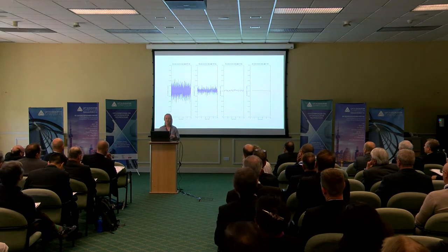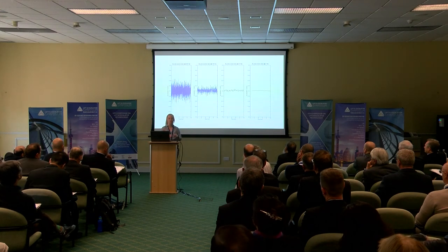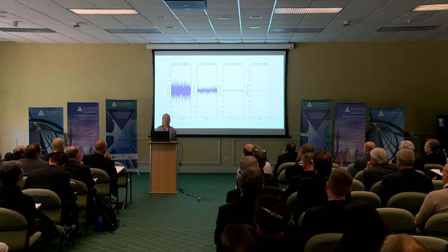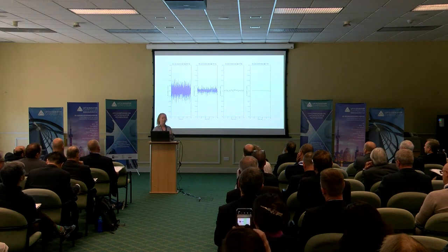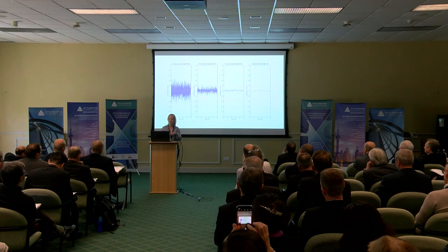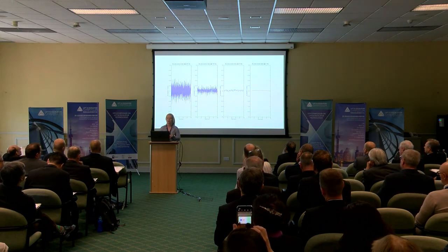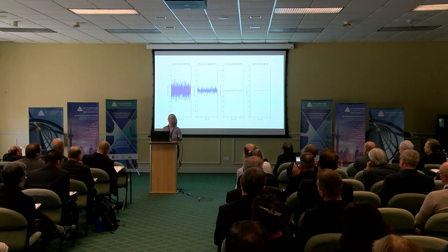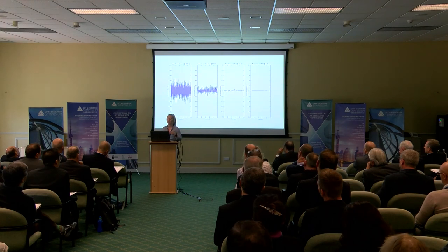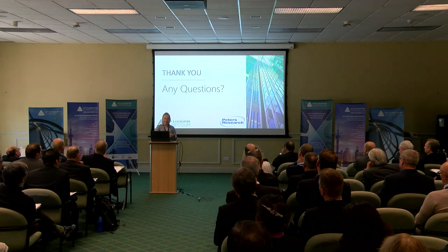It must be noted that there's a relationship between noise and sampling frequency — it's possible to reduce the noise level by lowering the sampling frequency, as illustrated in the image. An investigation into the optimal sampling frequency and minimum resolution in relation to this application would be worthwhile, to minimise noise without compromising identification of the key phases of the acceleration profile. We're currently investigating whether a higher-quality accelerometer with a finer resolution would enable the spatial plots of high-rise buildings with express zones to be determined accurately. Thank you for joining us today.